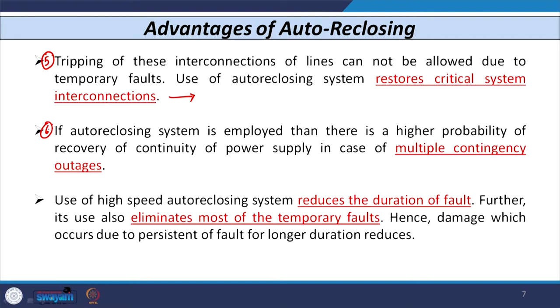Auto reclosing is also beneficial in case of multiple contingency outages. Furthermore, high-speed auto reclosers reduce the duration of a fault — the time the fault persists in the system — and eliminate most temporary faults. The damage caused by persistence of a fault for a long time is also reduced. Because of all these advantages, utilities are now widely utilizing auto reclosers at both distribution and transmission levels.